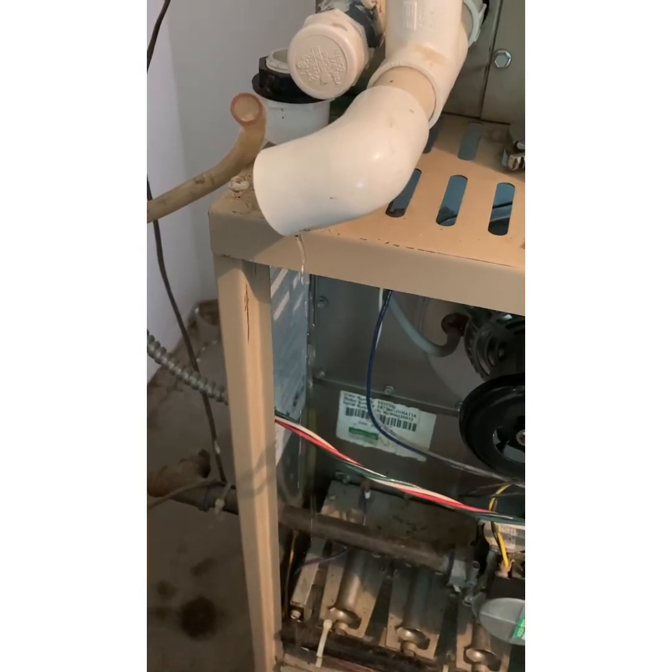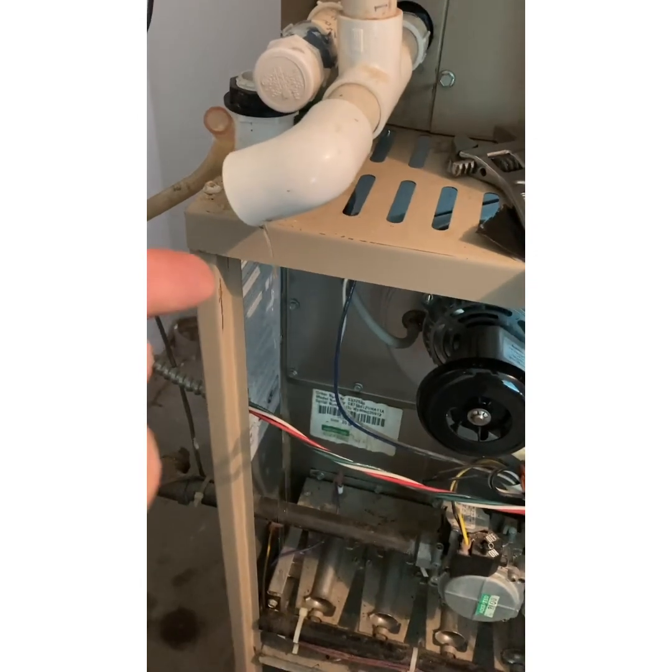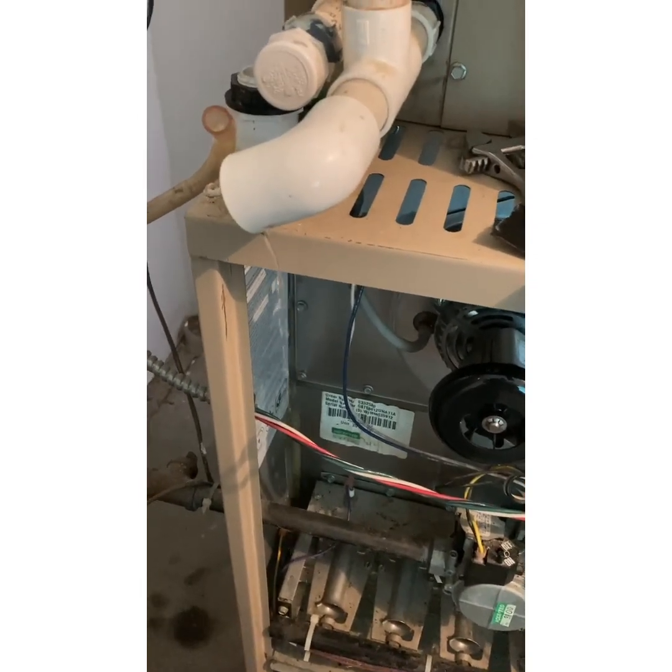So I took that 3/4 pipe coming out of the air handler area, and I pointed it straight down with a bucket underneath. And take a look at this photo. Look at the water coming out now. So that's good. Hopefully that's what it was. Because you can imagine doing it all night long. There's significantly more water coming out than what my kids saw outside, because the fitting itself had garbage in it. It wasn't allowing it to drain.